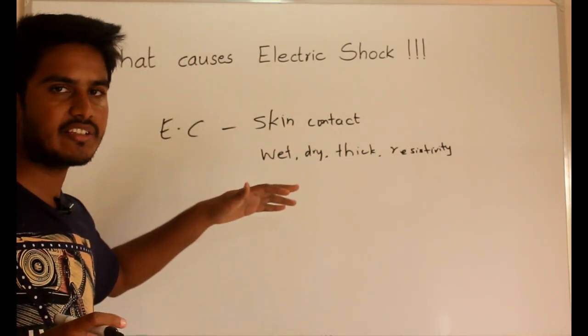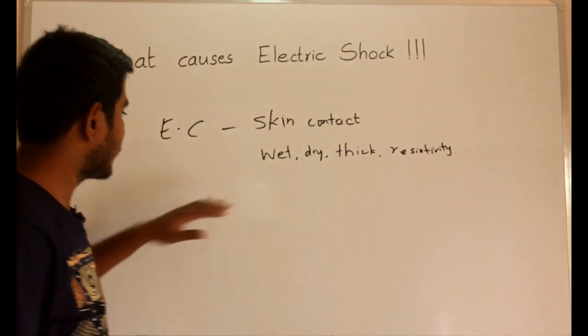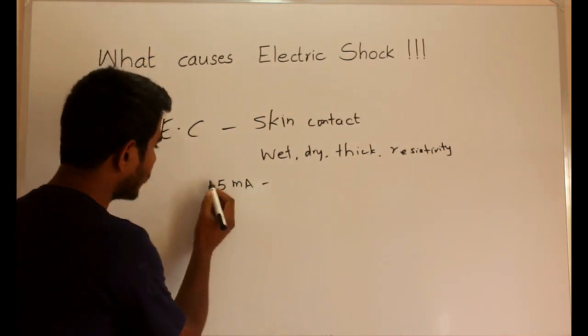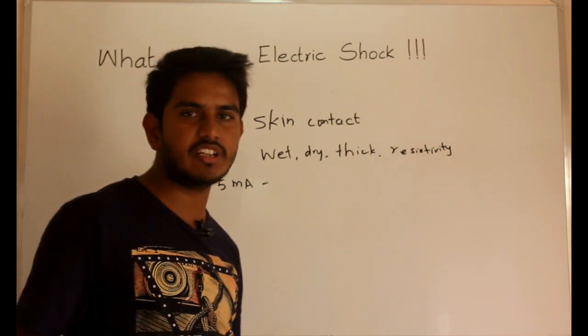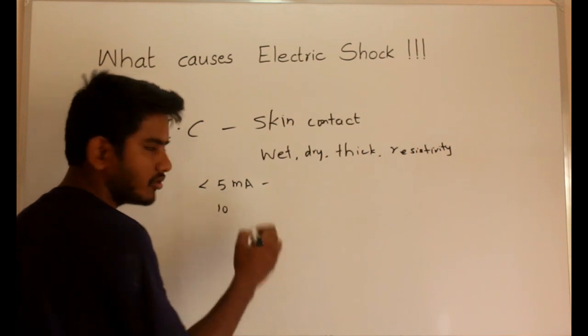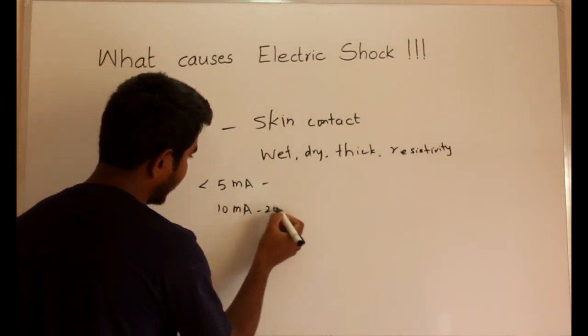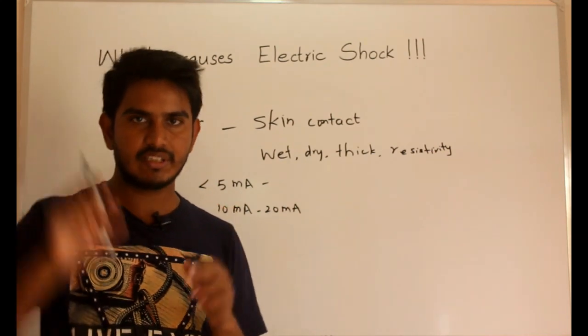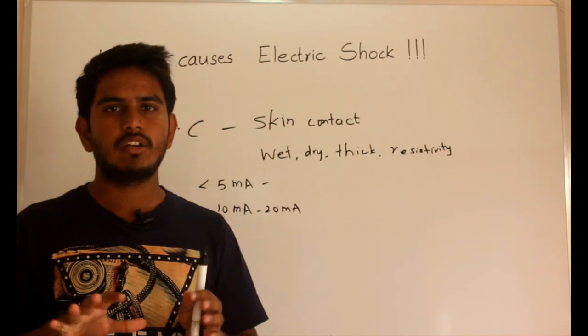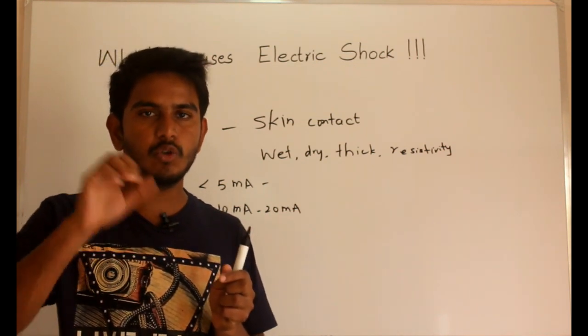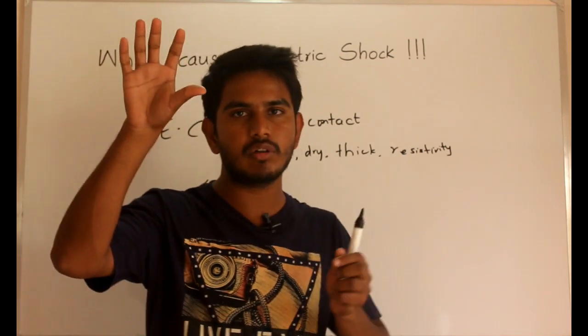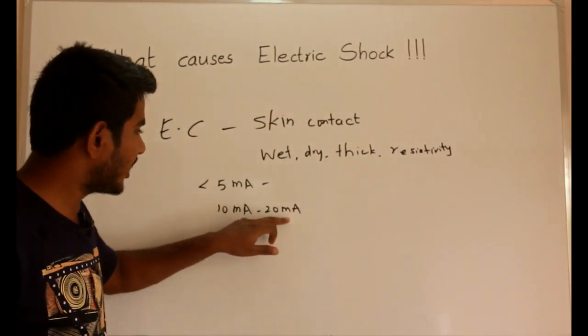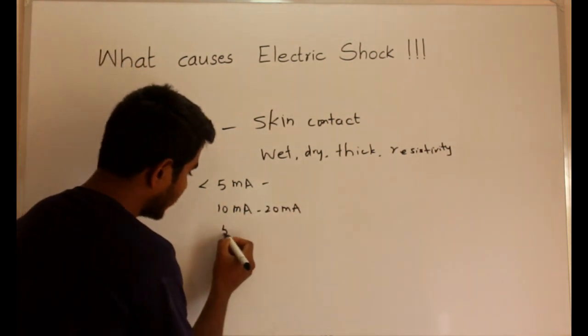If we classify the currents which are potentially dangerous and which are fatal to the human body: currents below 5 milliamperes are not potentially dangerous to the human body. If the current flowing through the human body is between 10 milliamperes and 20 milliamperes, then it is potentially dangerous because the victim loses muscular control. When you touch the electric wire, there will be contractions in your body and this prevents you from letting go.